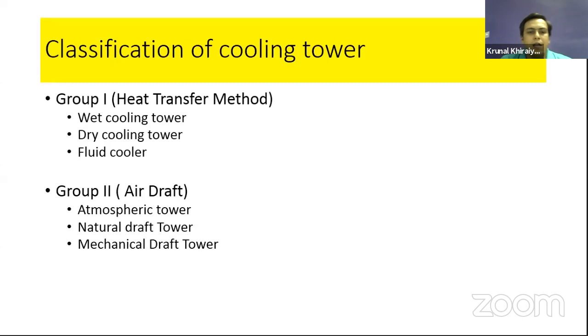Based on the air draft, we have classified cooling towers into three categories: atmospheric tower, natural draft tower, and mechanical draft. An atmospheric tower is only one kind of cube, and there is no change of shape. So there is no pressure difference created. The draft is near zero, because only atmospheric pressure is present inside and outside the cooling tower. This kind of cooling tower is called an atmospheric tower.